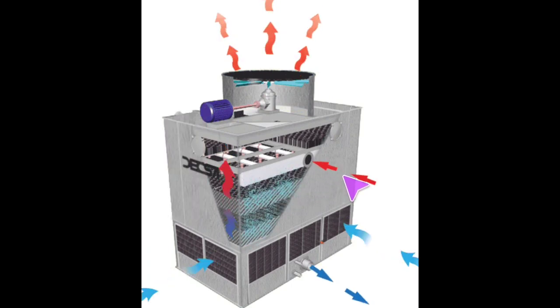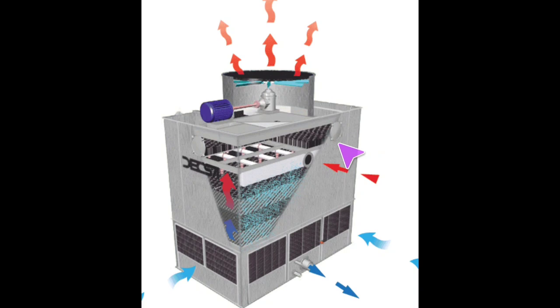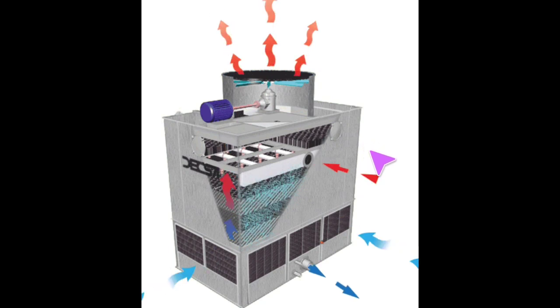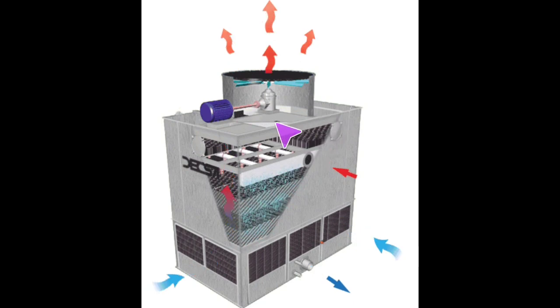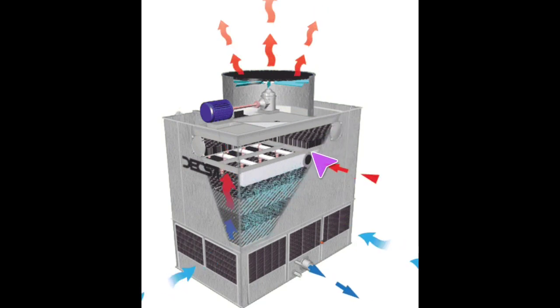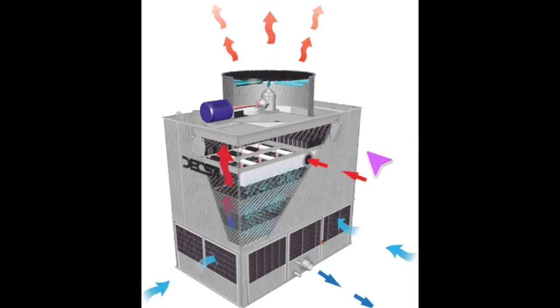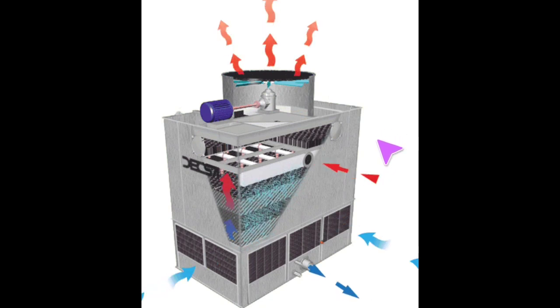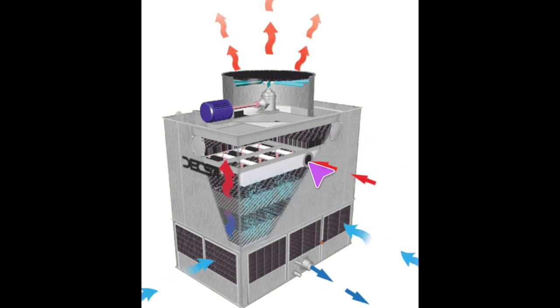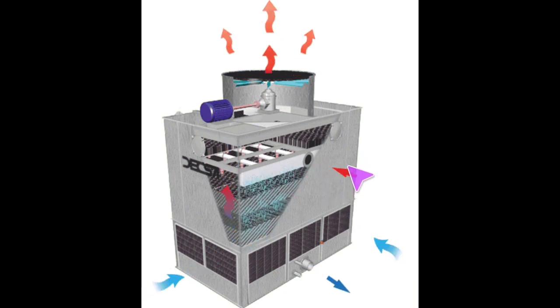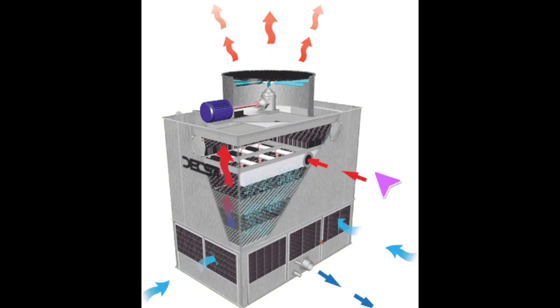Tower approach is the temperature at which the water is leaving the basin and the wet bulb temperature of the ambient air. When we start talking about what kind of set points we should be using, we're going to really focus on the centrifugal side because that's where things get the most sensitive. The other types of equipment like self-contained units and water source heat pumps have a lot of their own variables that we won't go crazy into depth on here.